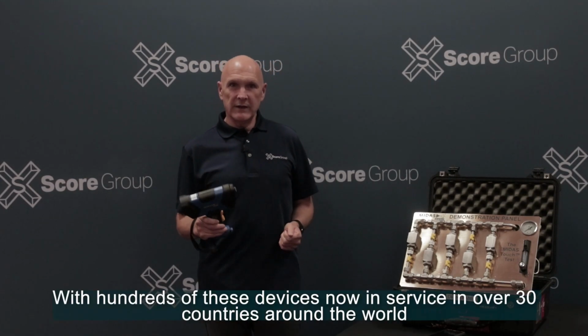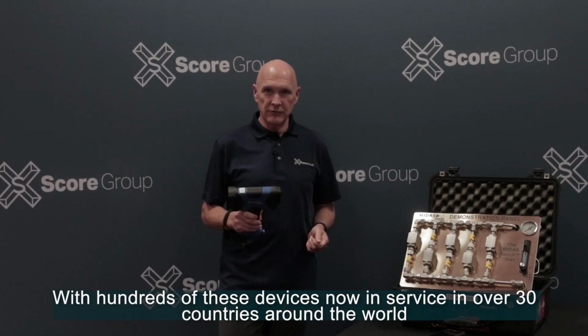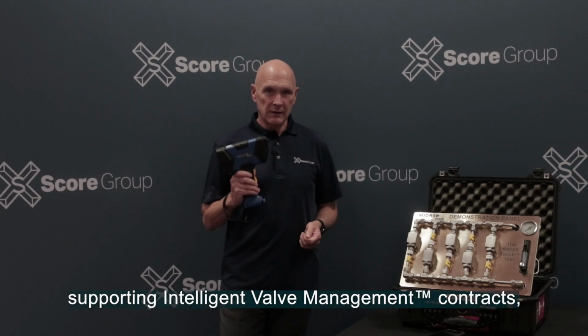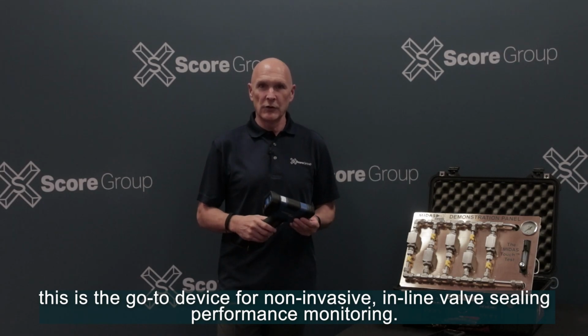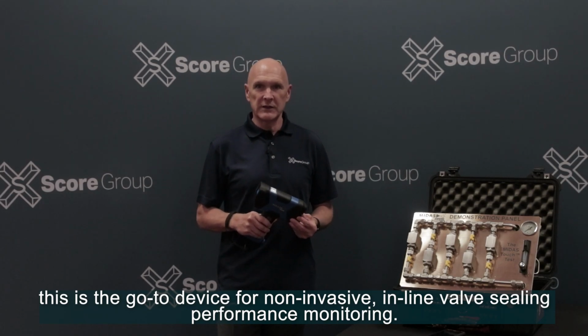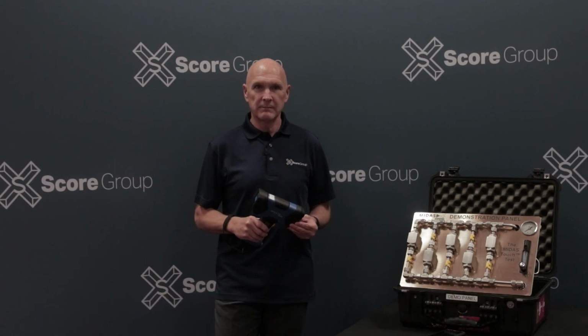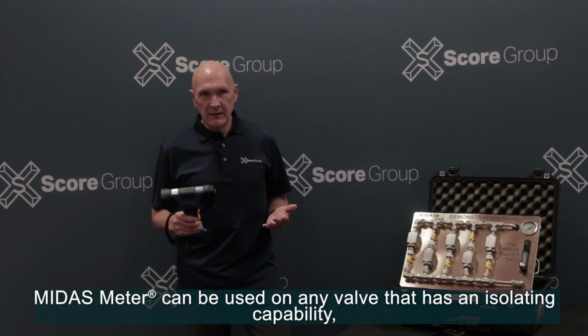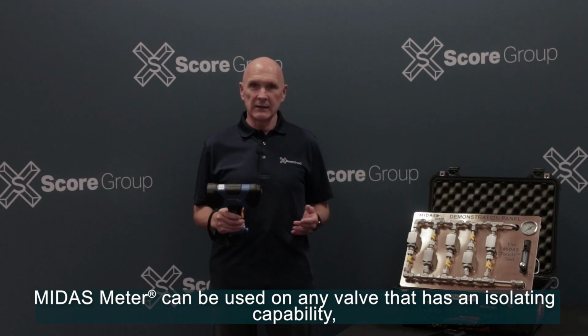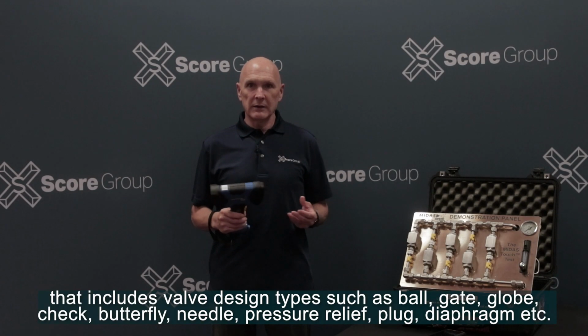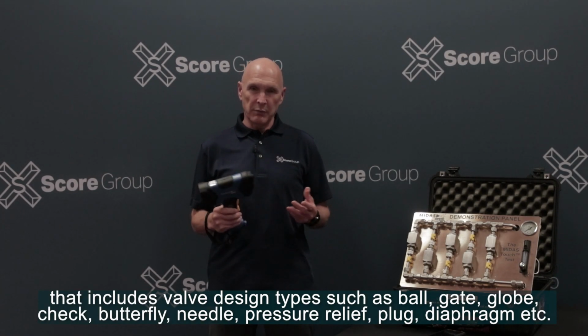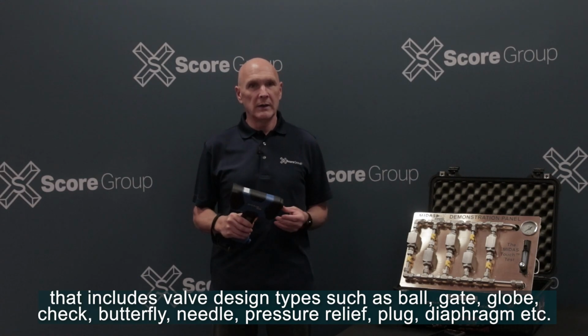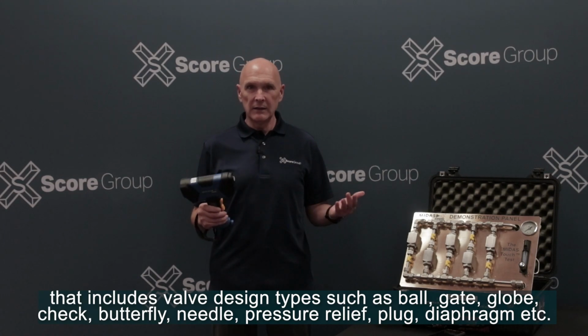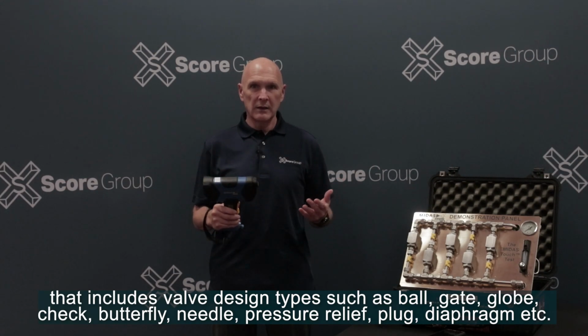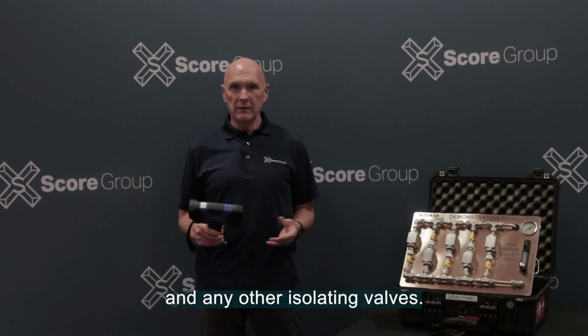With hundreds of these devices now in service in over 30 countries around the world, supporting intelligent valve management contracts, this is the go-to device for non-invasive, in-line valve sealing performance monitoring. MIDAS meter can be used on any valve that has an isolating capability.